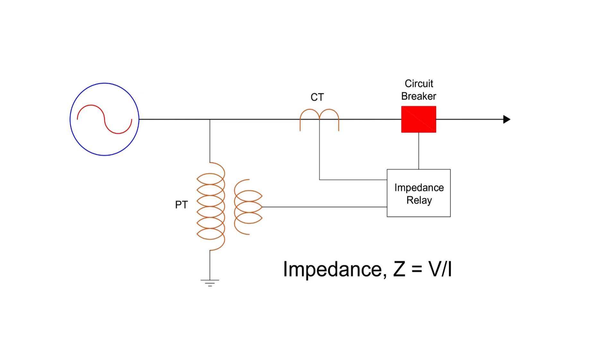Distance relays measure the apparent impedance from the relay's location to a fault. This is done by dividing the voltage at the relay point by the measured current. Z = V / I. If the measured impedance is less than the relay's preset value, the relay interprets this as a fault and sends a trip command to the breaker. The relay can operate directly or through a master trip relay for multipole tripping.